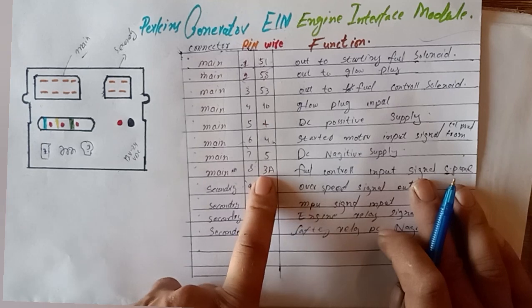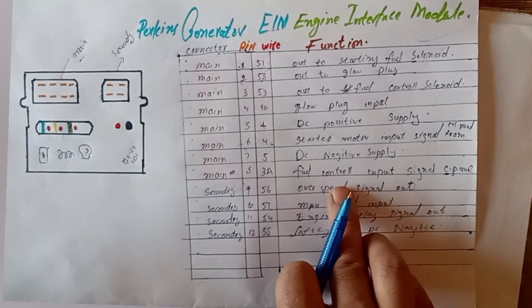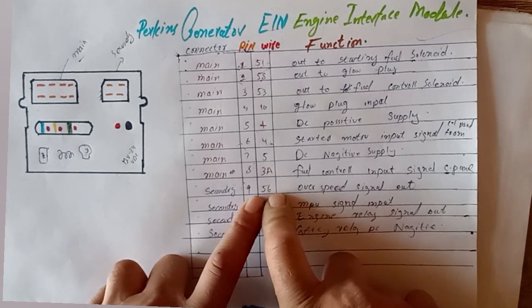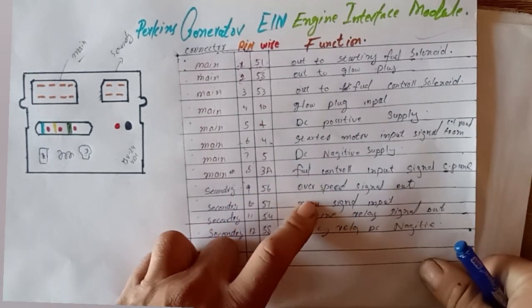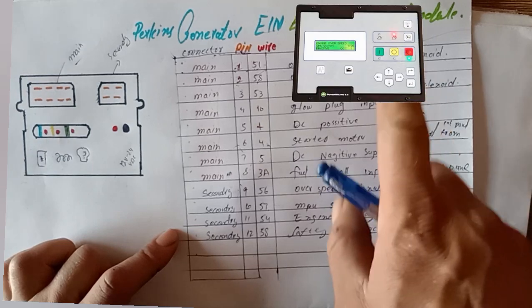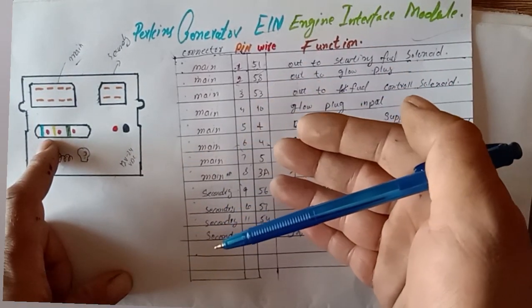Pin eight carries the fuel control input signal from the control panel, meaning the fuel pump control signal. Wire number 56 in the secondary port is the speed signal output — this is the output from the controller to your generator control panel. If the generator overspeeds beyond set parameters, this signal will trigger an overspeed display on your control panel screen and shut the generator down.